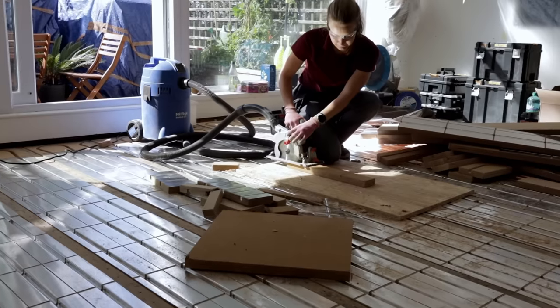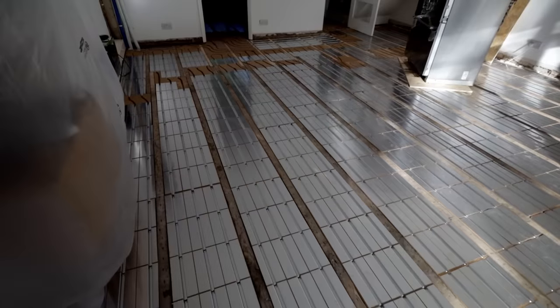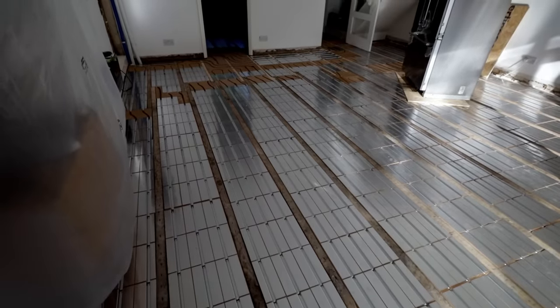Downstairs the floor is ready for laying the pipework, and this system looks super great quality. However, this is niggle number one: it is the most labor-intensive underfloor heating system I've ever come across. Almost three days to prepare 50 square meters of floor area — just laying the panels, cutting them to size, routing blank panels. A screed system would take about half a day, an overlay system maybe a day to a day and a half. This system takes twice as long as other comparable systems.